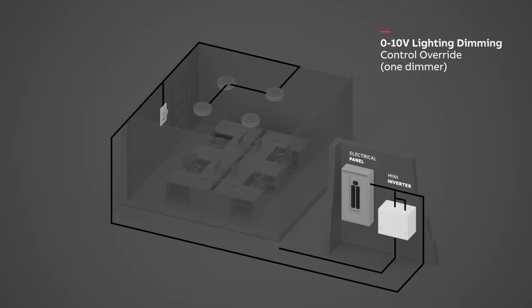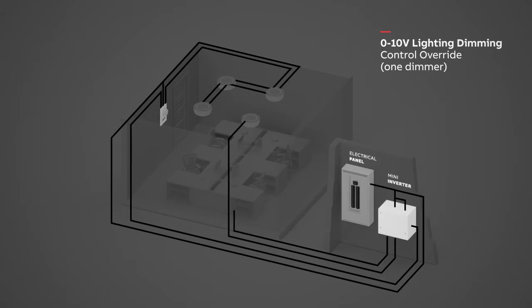Wire the Mini Inverter to the light that will be used as emergency light. Connect the wall dimmer to the lights that will not be used as emergency lights. Connect the wall dimmer to the Mini Inverter LCO Module. Wire the LCO to the light that is being used as emergency.